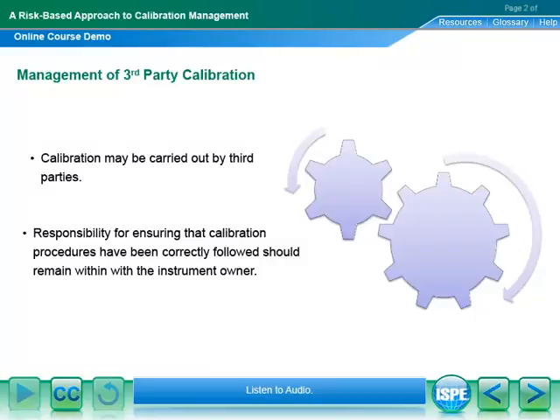Calibration may be carried out by third parties, but ensuring that calibration procedures have been correctly followed should remain with the instrument owner. The instrument owner can be the equipment user, the pharmaceutical manufacturer, or the company who is subject to regulatory control.